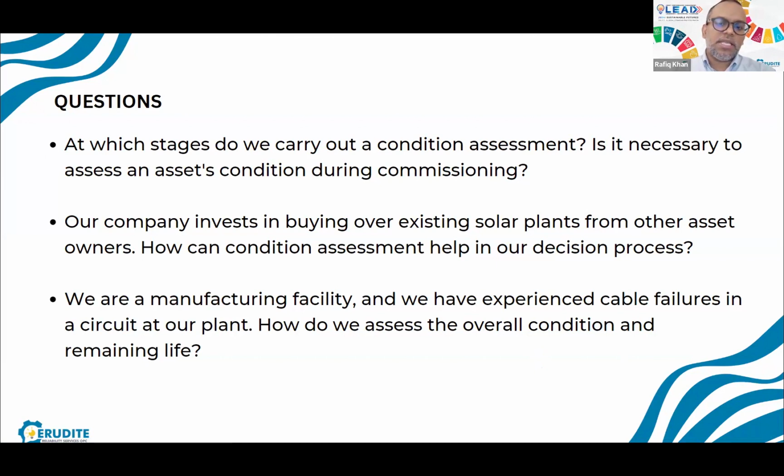So what we offered them as an organization was to do a condition and remaining life assessment, but also to pair it together with failure investigations. So they do some form of test, which we already listed just now, and we analyzed this data. Some of the cables which failed, they stored. And so these were valuable information providers for us.